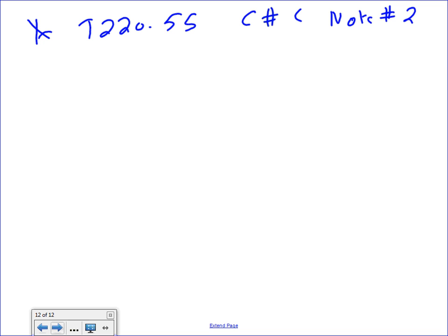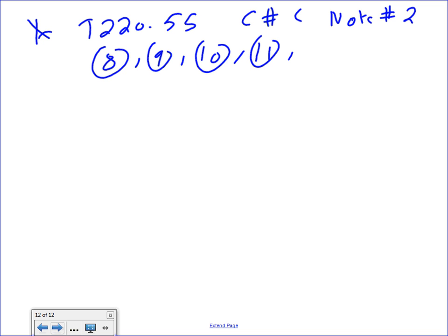That applies to 8, 9, 10, 11, 12, and 13. All these branch circuits apply to all of them. Okay, let's go do it. Anything less than 12, what do you do with it? Make it 12. So the code says make everything 12, average them. So first of all, let's see how many of them do we have first.